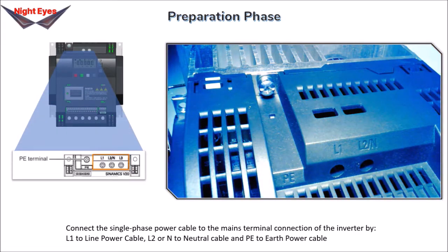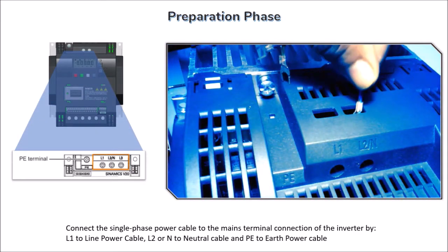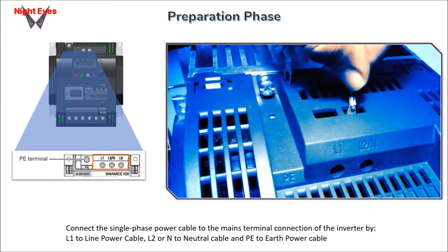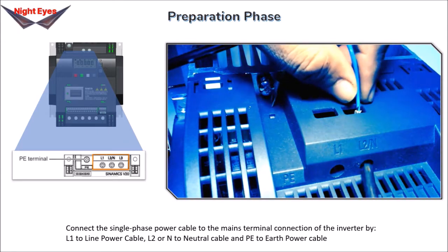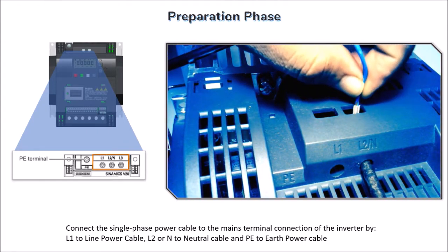Connect the single phase power cable to the mains terminal connection of the inverter: L1 to the line power cable, L2 or N to the neutral cable, and PE to the earth power cable.